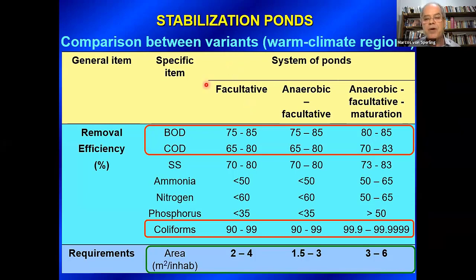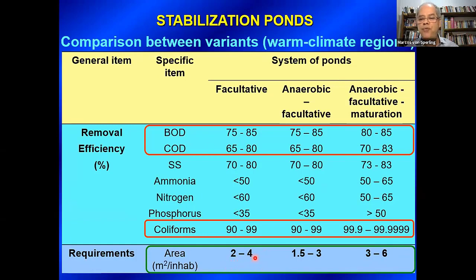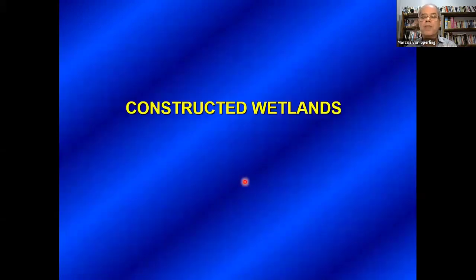This is a summary of typical removal efficiencies for the main pond arrangements in terms of BOD, COD, and coliforms. The removal efficiencies are not spectacular — in the range of 75% to 85% for BOD, slightly less for COD. We are not able to remove suspended solids and nutrients well in these typical arrangements, but we are able to remove coliforms very well, especially if we incorporate maturation ponds. Land requirements in warm climate countries are between two to four square meters per inhabitant for a facultative pond, and more if maturation ponds are incorporated.